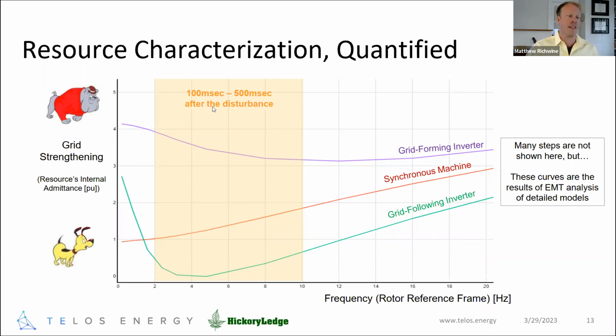The last thing I wanted to point out is this orange shaded portion of the curve, 2 to 10 hertz in the frequency domain, or roughly 100 to 500 milliseconds in the time domain after the disturbance. That's an empirical view of the critical band important for voltage stability on the system — where in this frequency domain we should pay the most attention, particularly when the value isn't constant across the domain. Our empirical results indicate it's those first couple hundred milliseconds after the event where you can control voltage. That's why I've highlighted it here in the frequency domain.